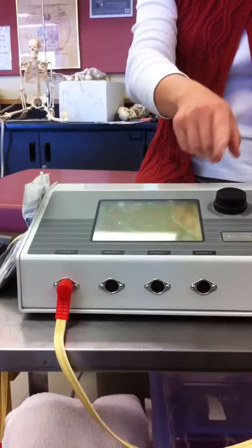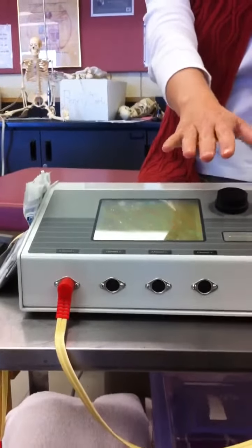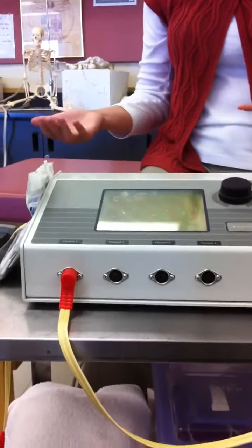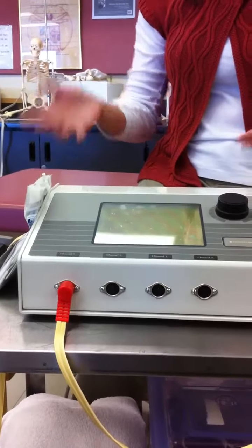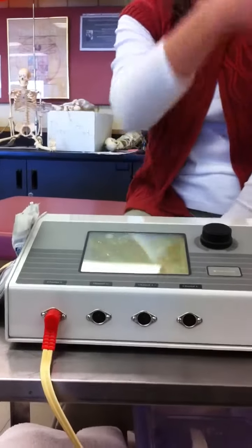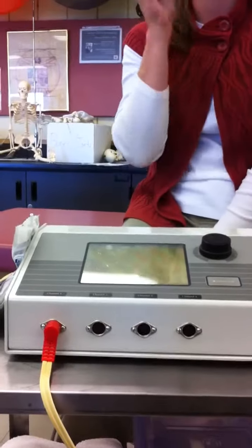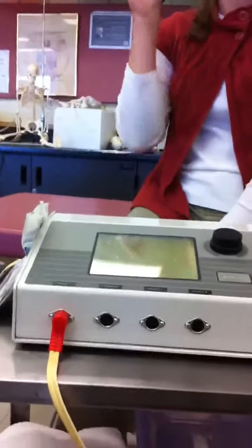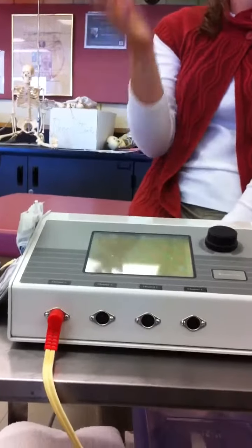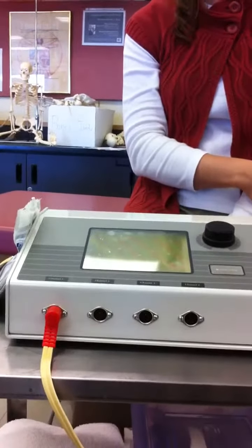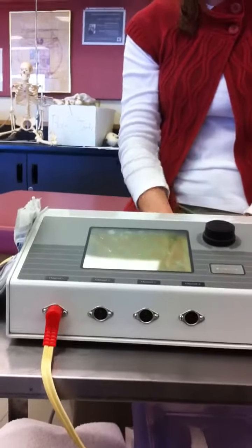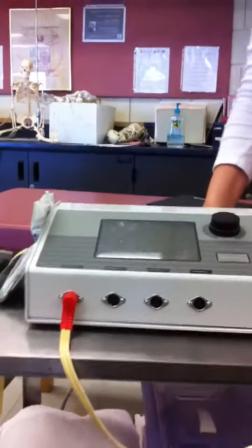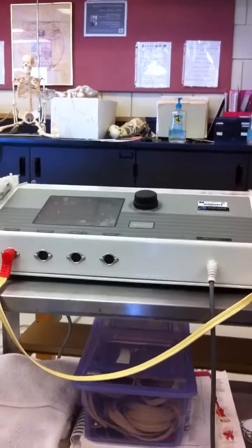Okay? When you depress the button after setting the max current, the patient will go, oh, wait a minute, it's gone, it went away. Yeah, that's what's going to happen until you answer that question no, and then the clock's going to start, and the time and the ramp is already preset in here. Okay, so it will ramp up, contract. After 10 seconds, it will relax. Okay, so that's this machine, the TheraTouch. Nothing to edit.